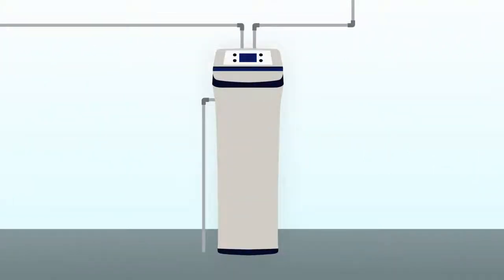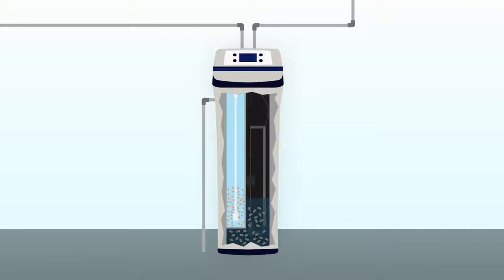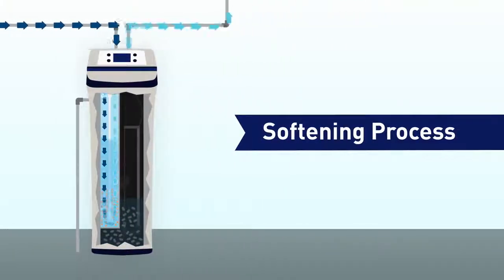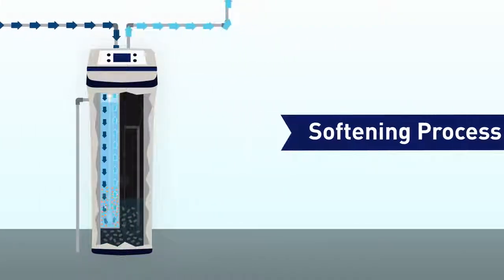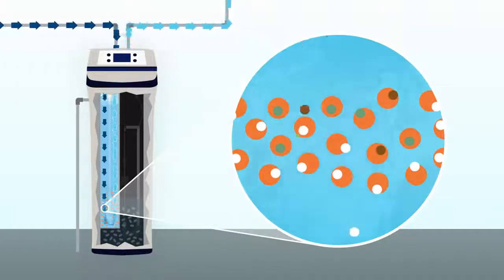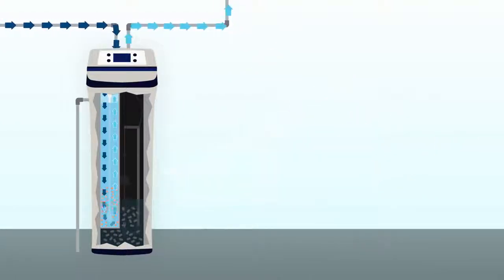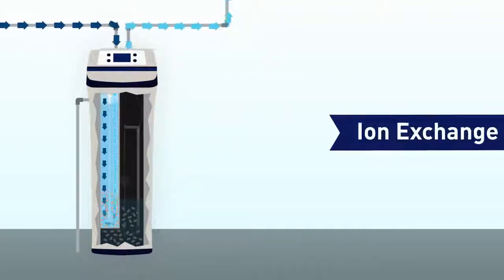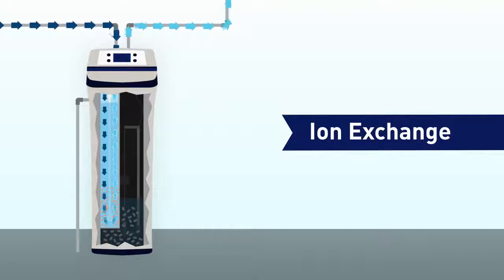When water enters your home, the first stage of softening begins in the resin tank. Water circulates in the tank, where tiny sodium-covered resin beads swap the calcium and magnesium in the water for the sodium they're holding. The beads act as a scrubber, removing the hardness minerals out of your water. This process is referred to as ion exchange, and soft water is the result.